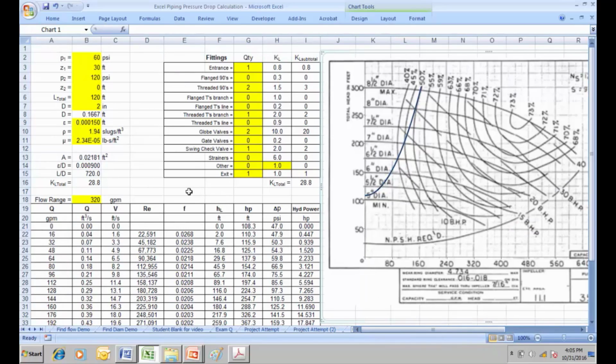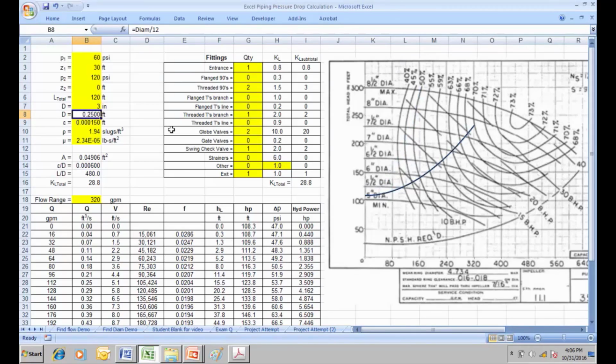Anyway, so these are different impeller diameters for the same pump housing, and I'm going to change my system curve around here just a little bit, because let's say I have a 3-inch pipe instead of a 2-inch pipe. You could see, okay, that makes sense. Now perhaps we had a system with a 7-inch diameter impeller, and for the system that we're describing up here with the 3-inch pipe, it would operate at about 240 plus.